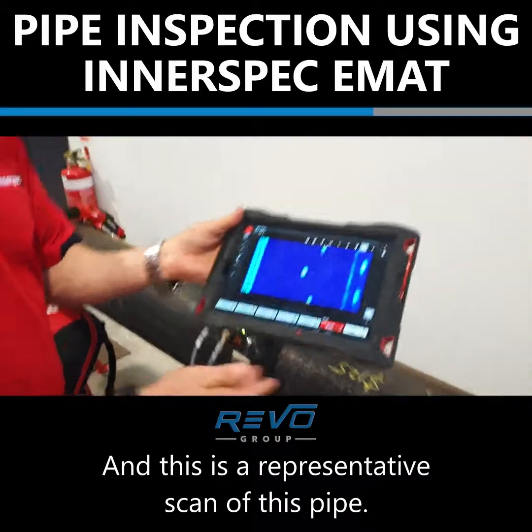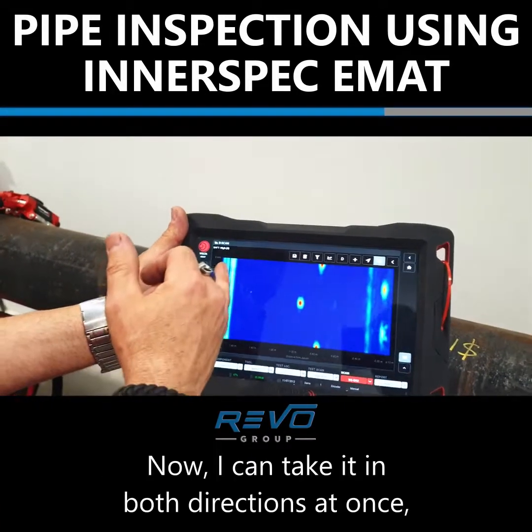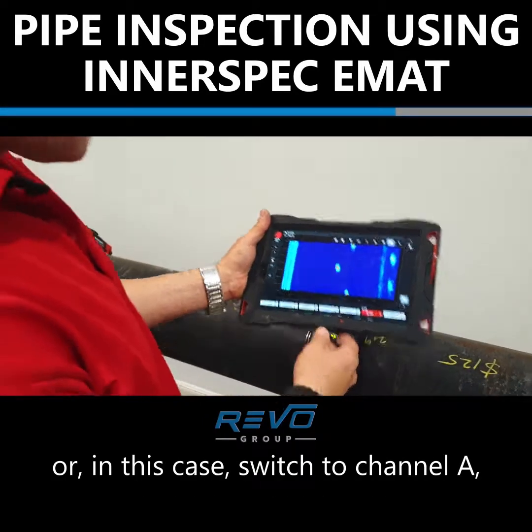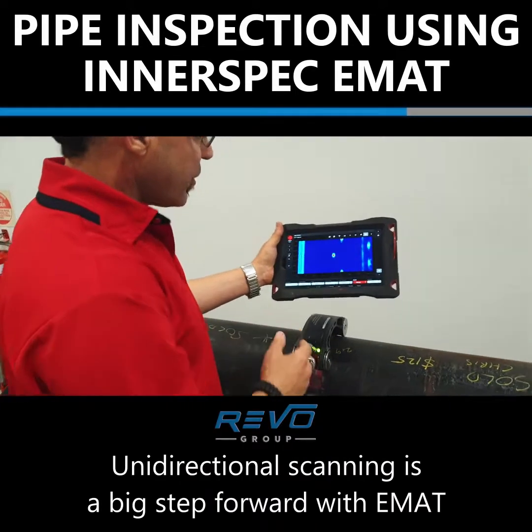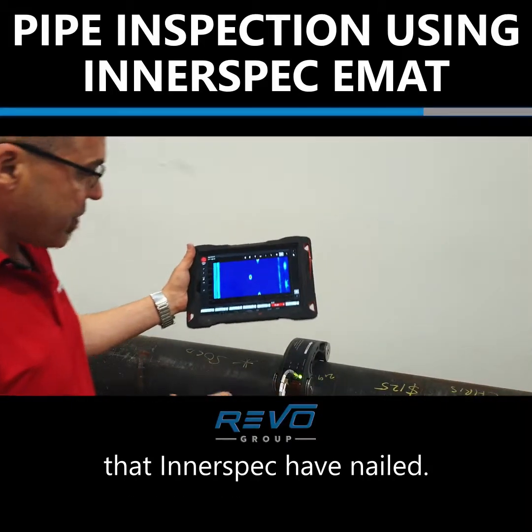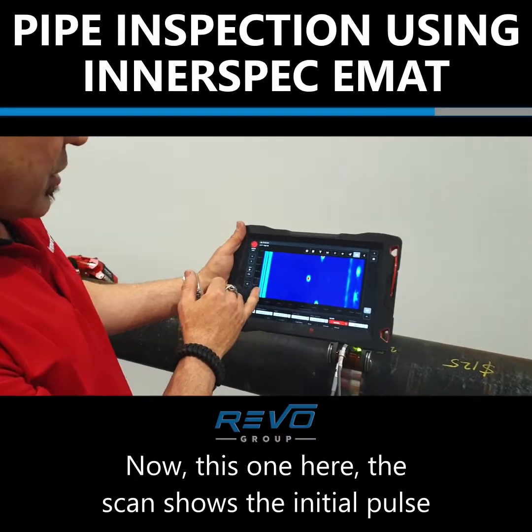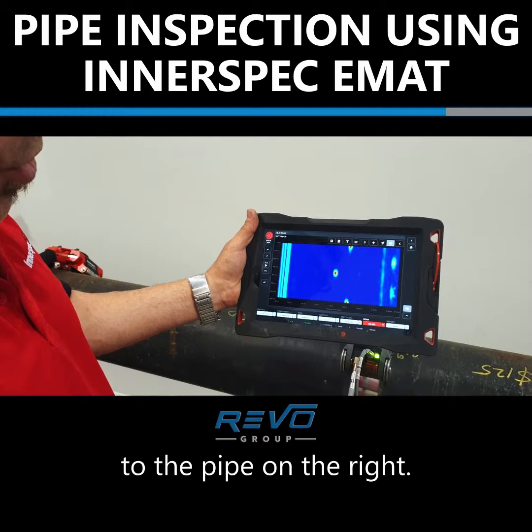This is a representative scan of this pipe. I can take it in both directions at once, or in this case switch to channel A looking in that direction or channel B in that direction. Unidirectional scanning is a big step forward with EMAT — Innerspec have nailed it. The scan shows the initial pulse on the left and the defects that we've introduced to the pipe on the right.